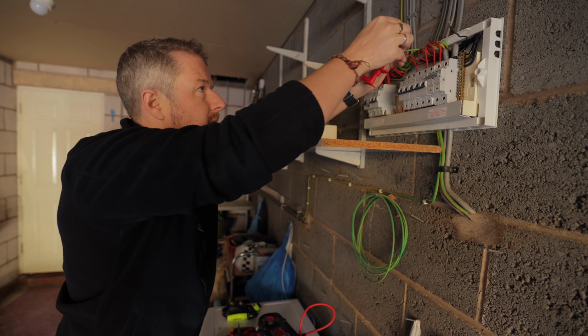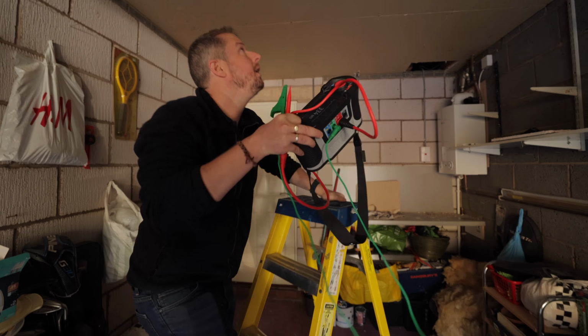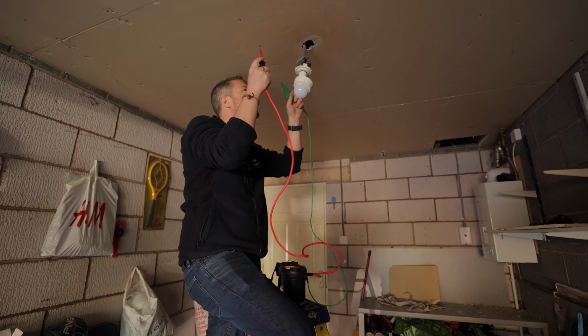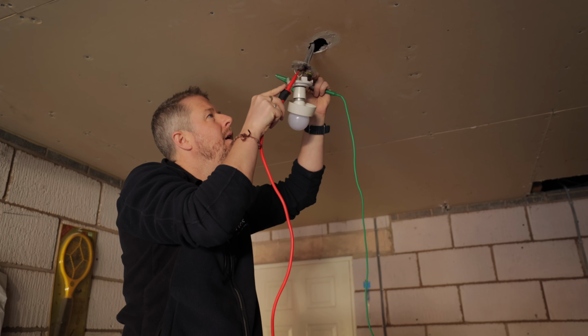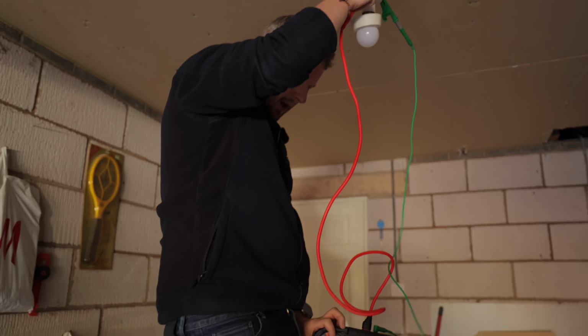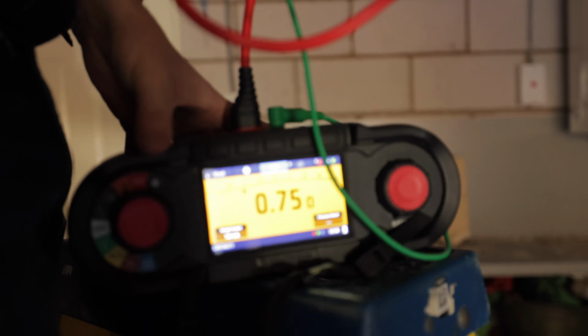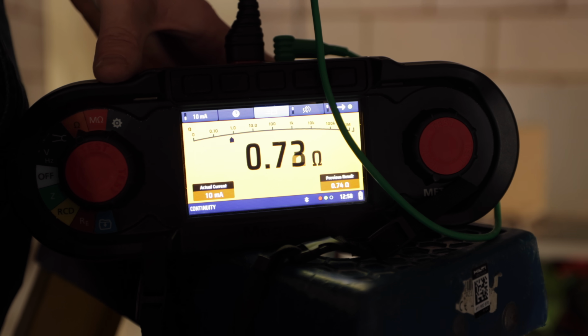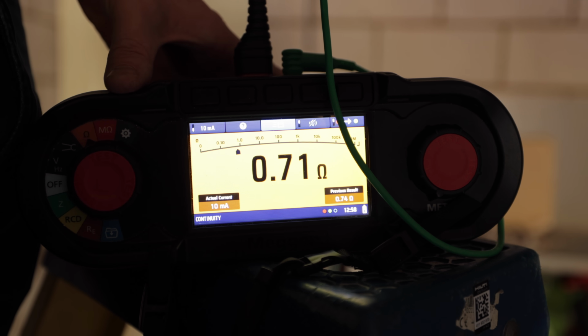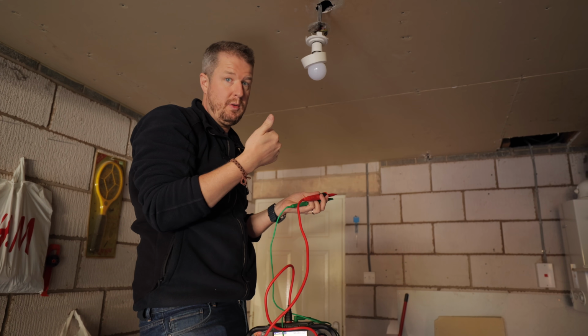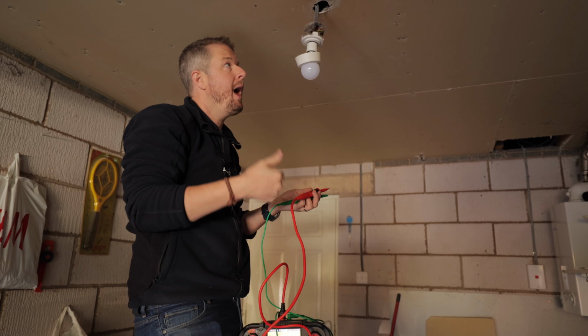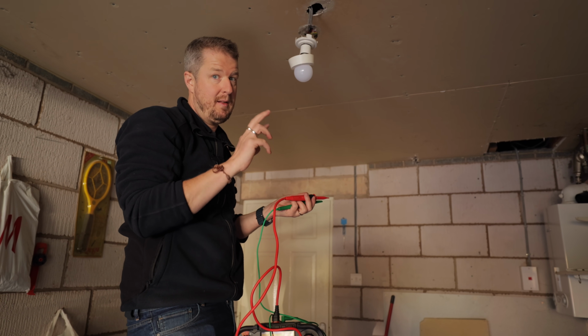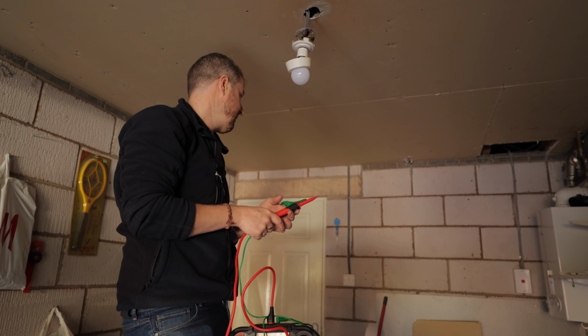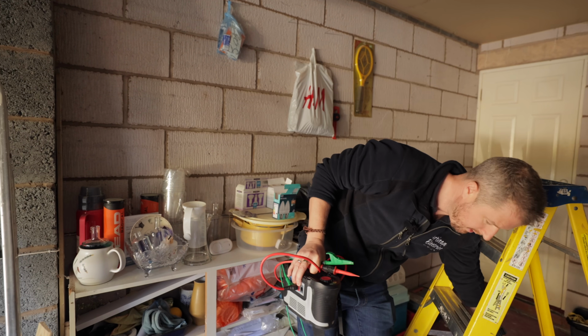So those are linked out, and then at every light we're going to test between live and earth, do a continuity test. All right, so this is what it should look like. At every light between live and earth there should be a low resistance like this, 0.72. It's confirming that we've got earth continuity, so we do have an earth at this light. Secondly, it's confirming the polarity, that the live and the neutral are not the wrong way around. So that's one light, but we need to check some other lights.